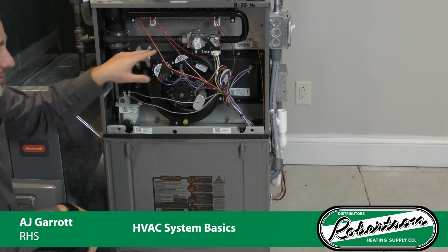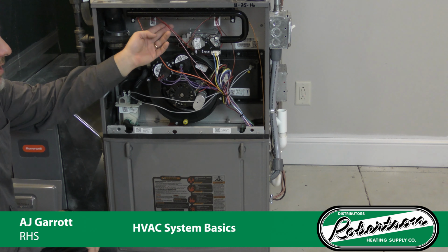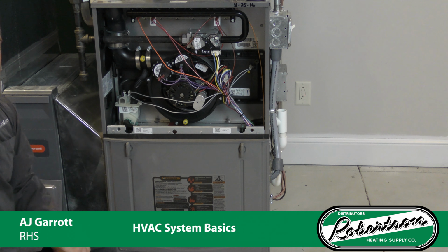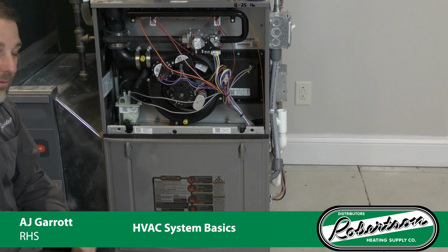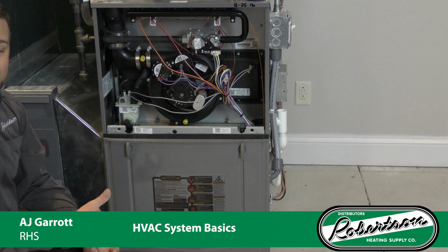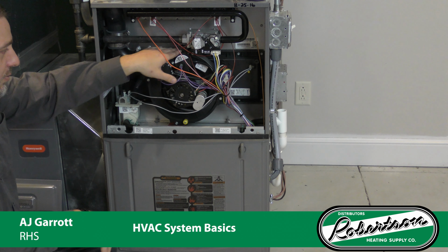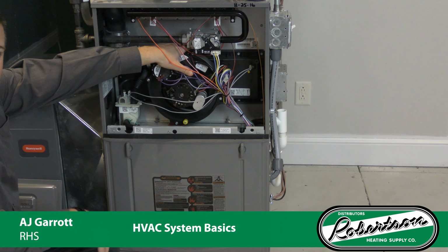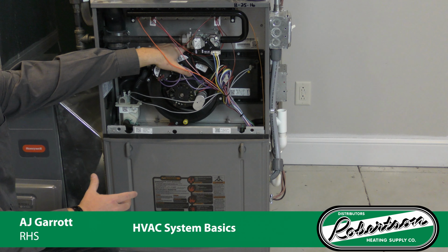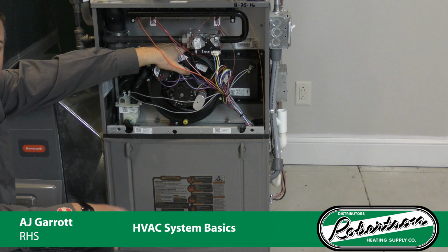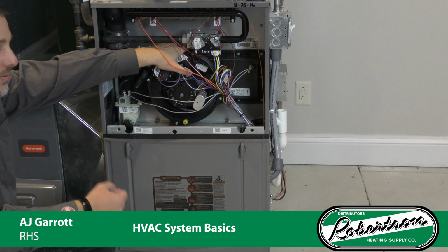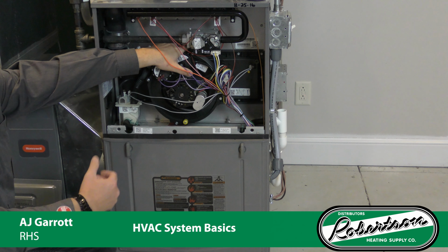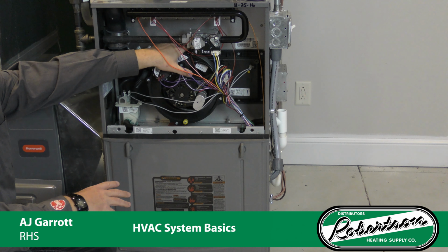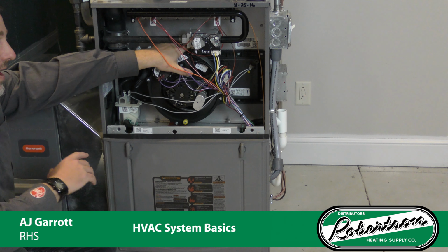We also have some safeties inside the furnace that are in these red wires here, and they are protecting the furnace from overheating. They're called limits. Limits, we have one looking at the main airflow to make sure it's not too hot. Maybe our blower motor goes bad and we're not passing air over it. Well, it gets too hot, and then at that point it'll shut off the furnace and keep it off for an extended period of time.